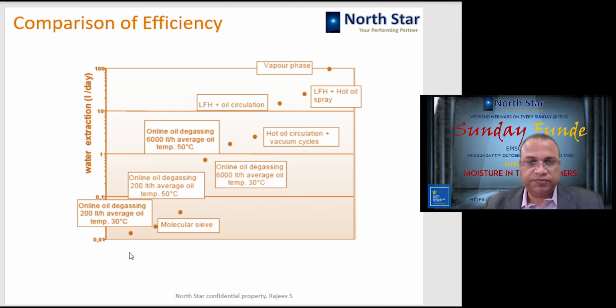And molecular sieves, which we have seen last, it is a very slow system, and it can take around 0.01 to 0.1 liters of moisture from the transformer in a day. Of course, it is a slow system, but since it is online, it is continuously doing it, so in turn it turns out to be more effective than all these methods. So if emergency situation is not there, then molecular sieve method is giving you long-term, long-lasting results.